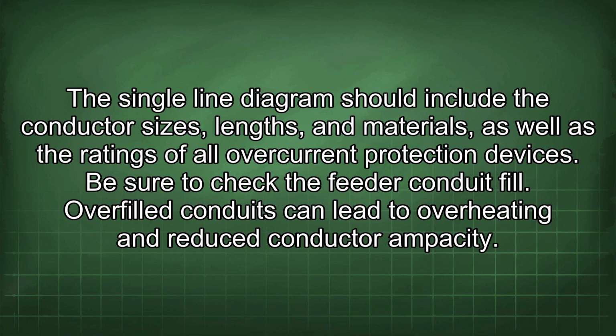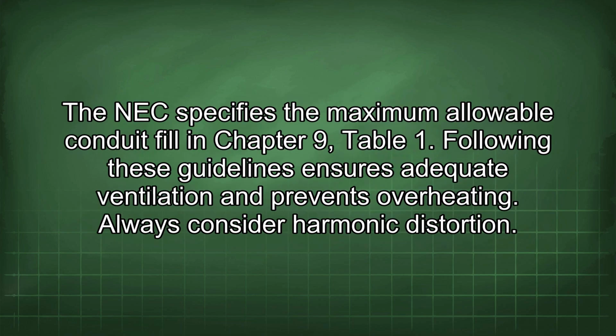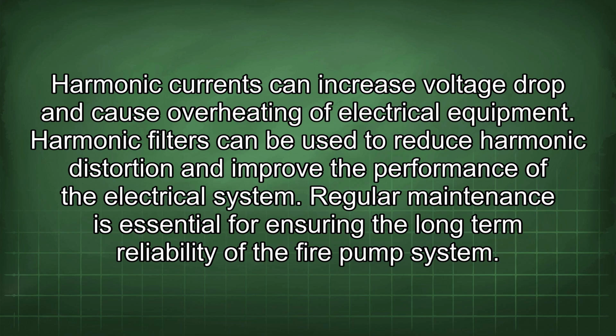Overfilled conduits can lead to overheating and reduce conductor ampacity. The NEC specifies the maximum allowable conduit fill in Chapter 9, Table 1. Following these guidelines ensures adequate ventilation and prevents overheating. Always consider harmonic distortion. Harmonic currents can increase voltage drop and cause overheating of electrical equipment. Harmonic filters can be used to reduce harmonic distortion and improve the performance of the electrical system.